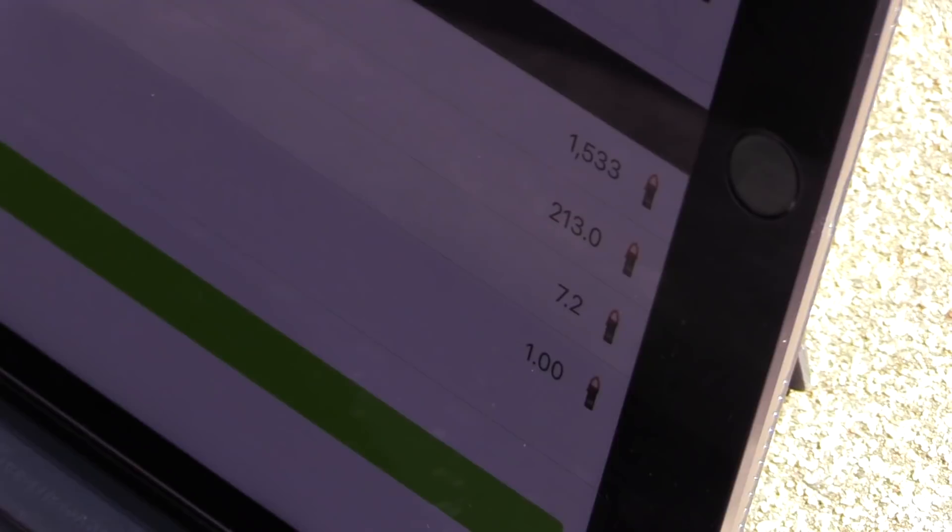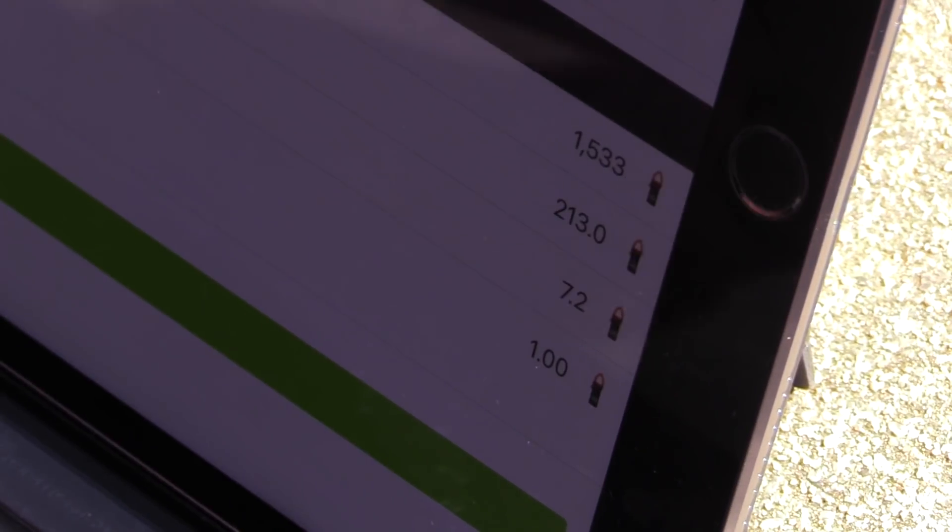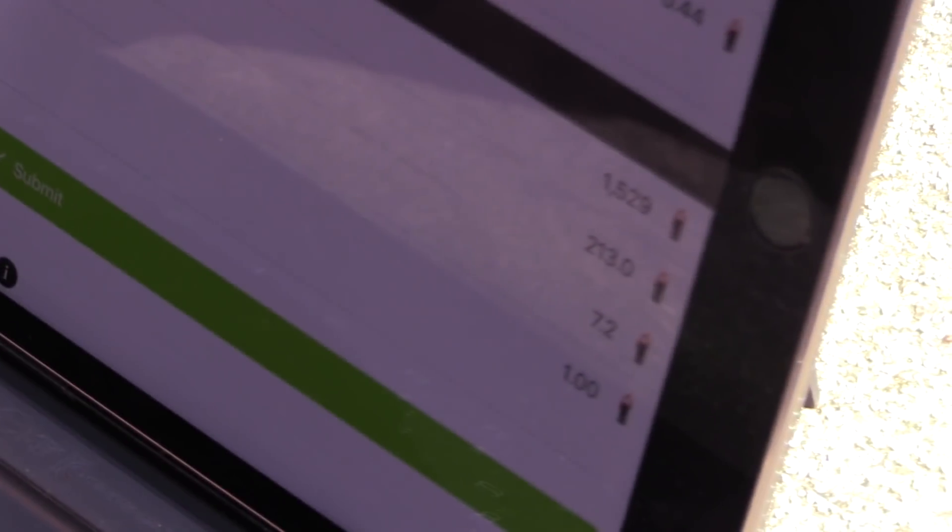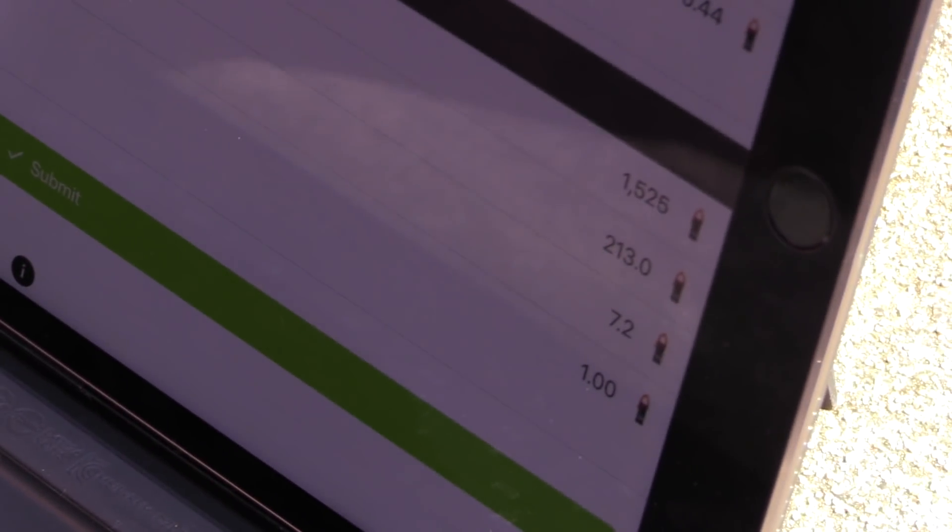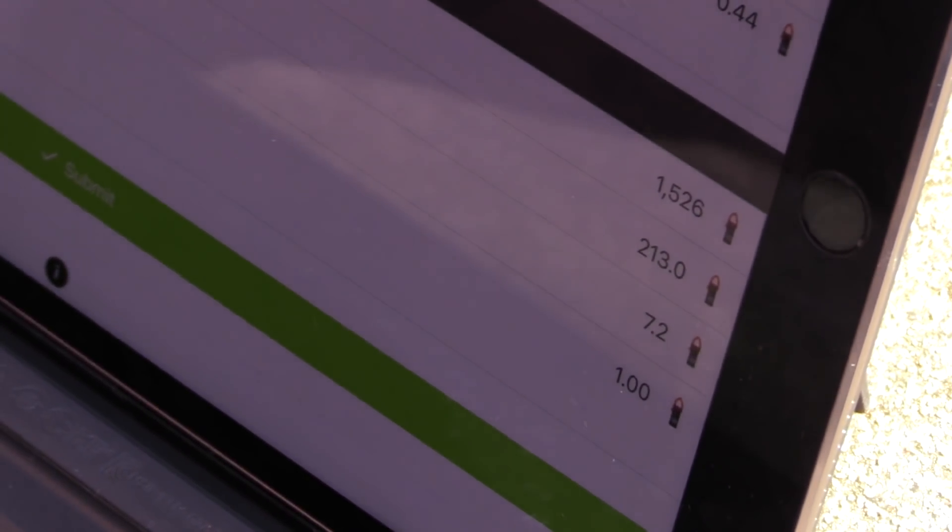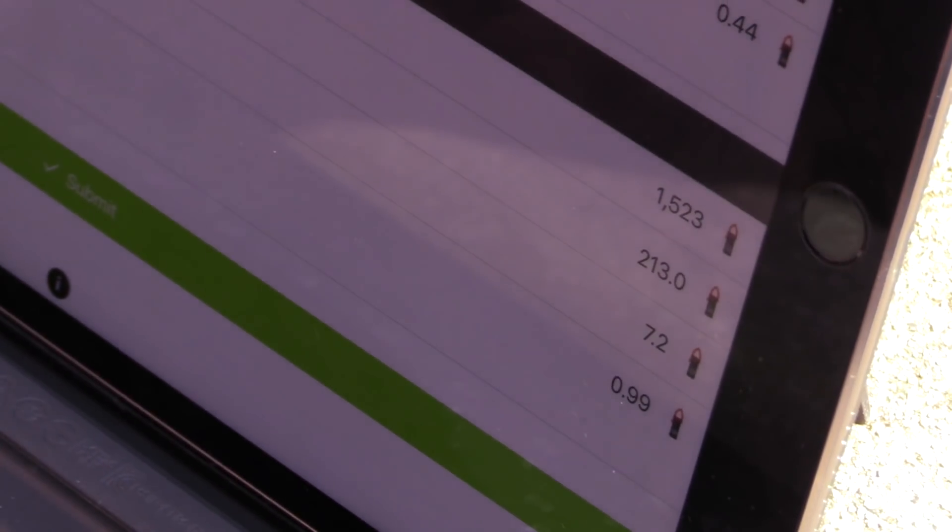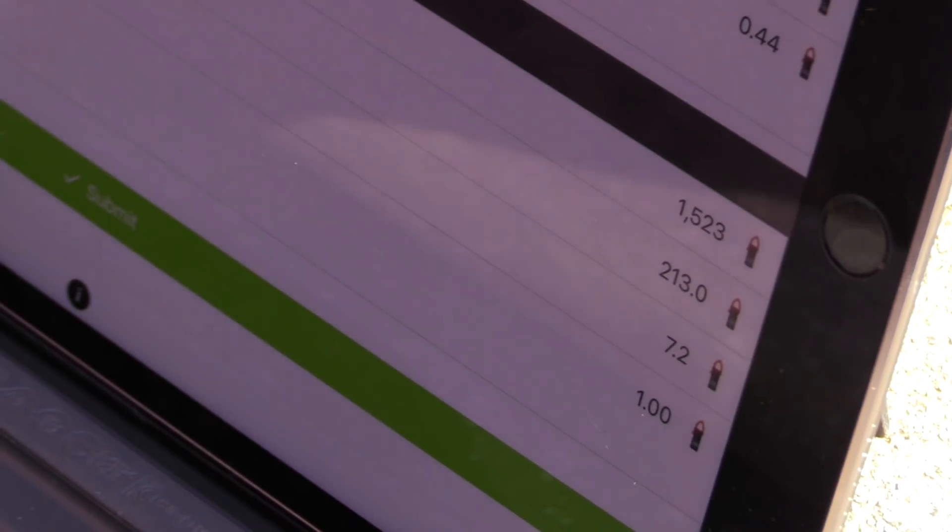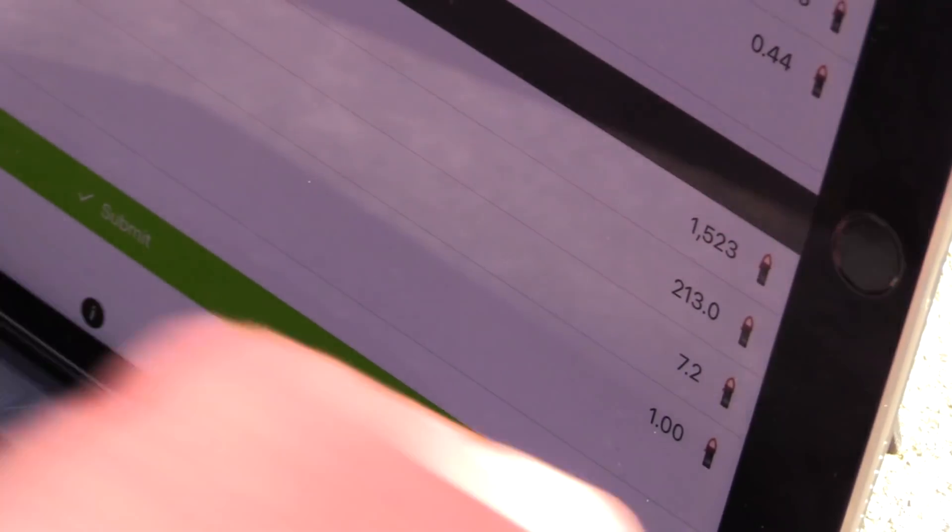This one's also got a really low power factor. Is this a digital compressor? Oh there we go, unity. Okay, I just must not have had it fully on there. Yep, so there we go. We'll hit capture here, and capture and clear. Let me hit capture, there we go.